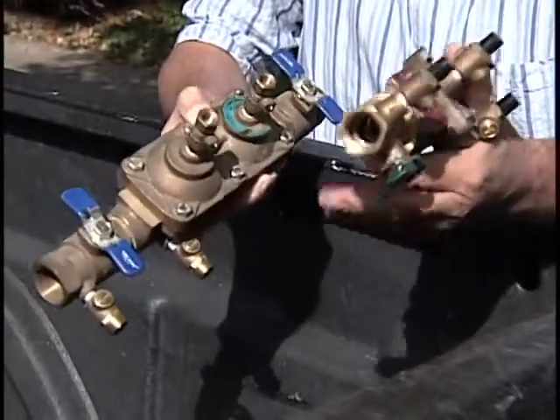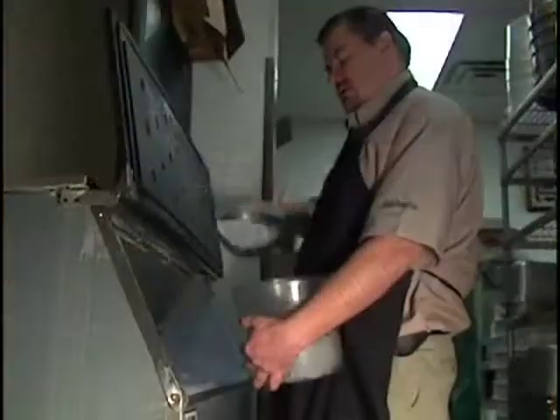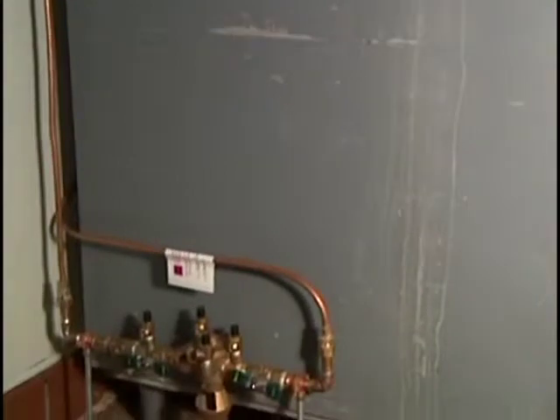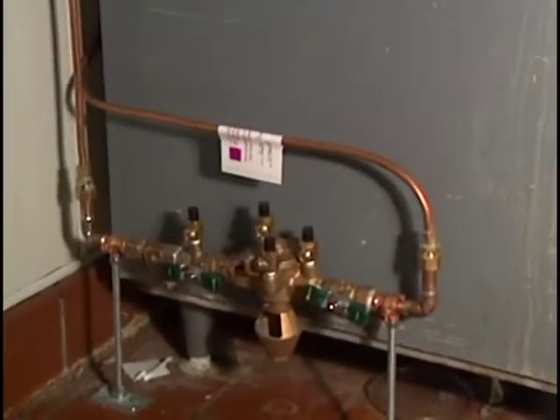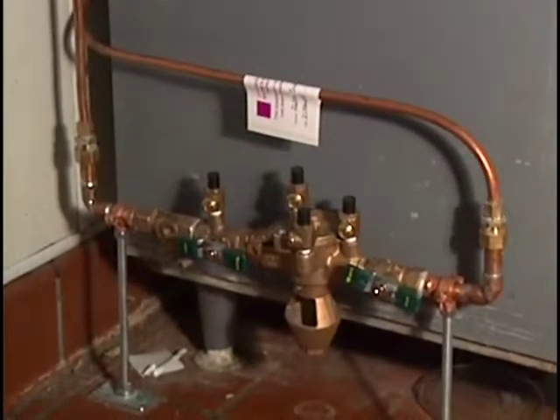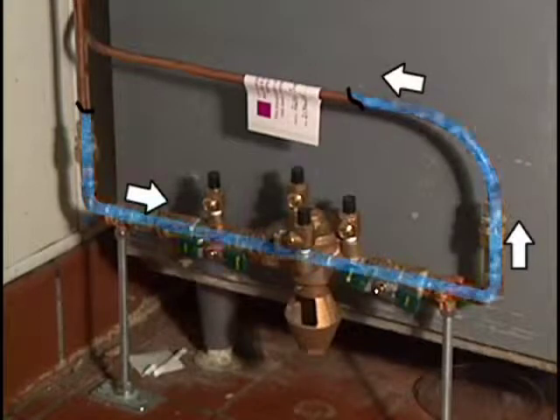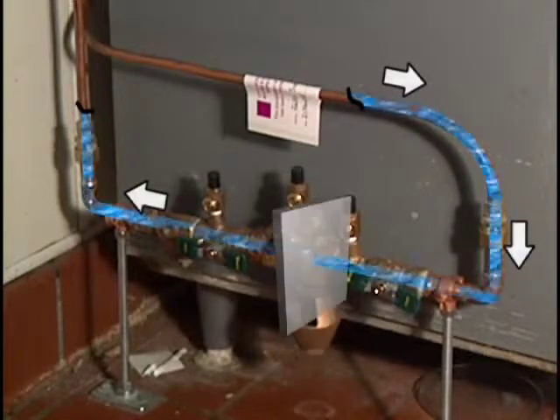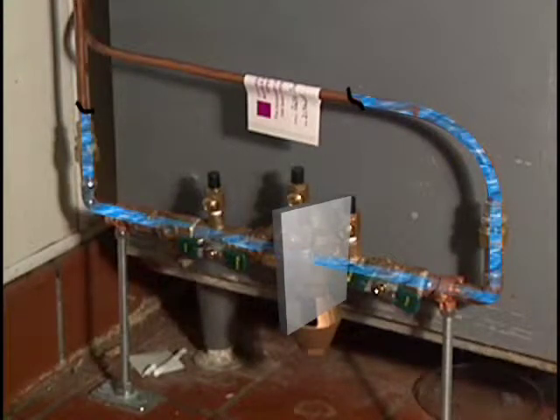These backflow prevention assemblies are testable to ensure they are working right. Placed at the site of a possible cross connection, they can protect the plumbing system from contamination. Placed just downstream of a water meter to an establishment, they can protect the public water system from any contamination that may occur within the entire establishment's plumbing system.